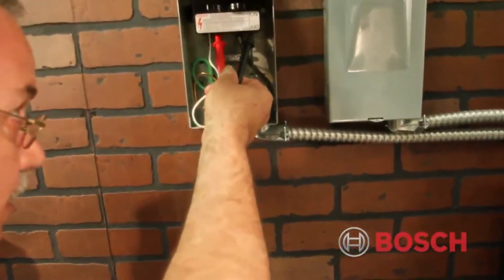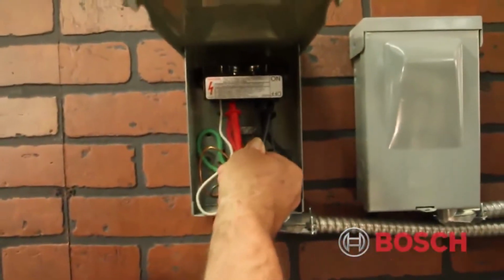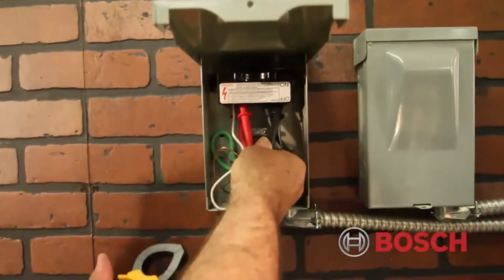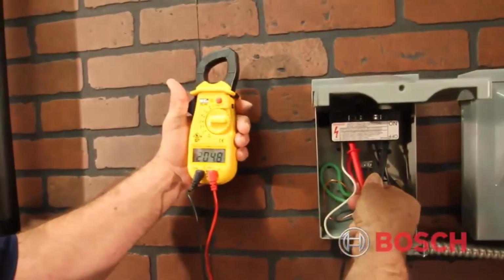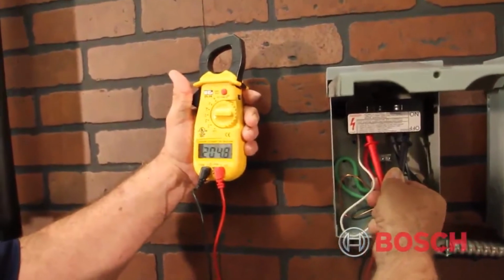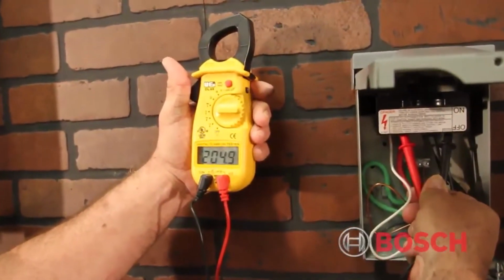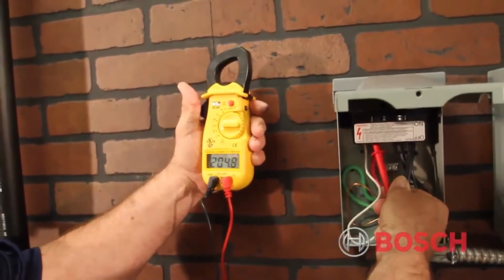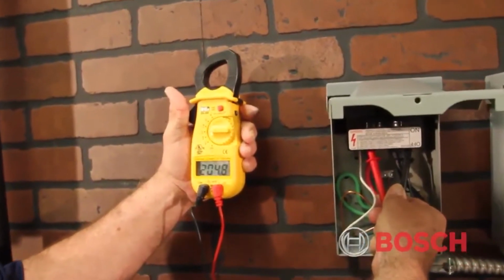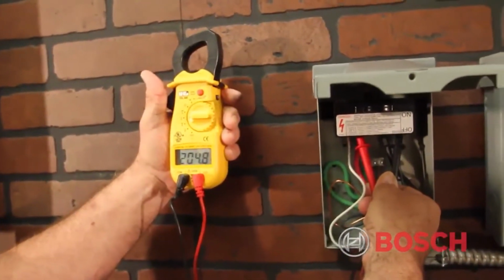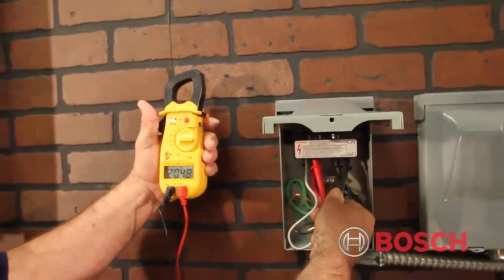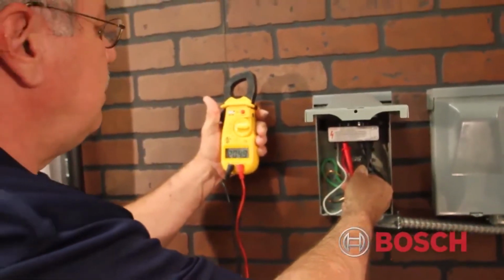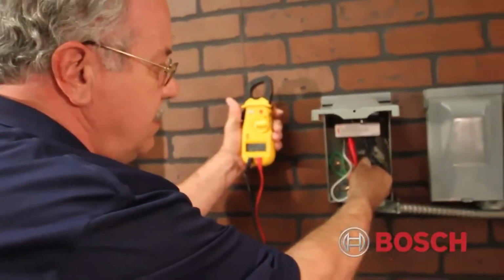I will check across L1 and L2 with the probes. And in this particular case, I see we are pulling around 205 volts. This particular transformer can be set for 208 or for 230 volt single phase 60 hertz. In this particular case, we're around 205 volts.